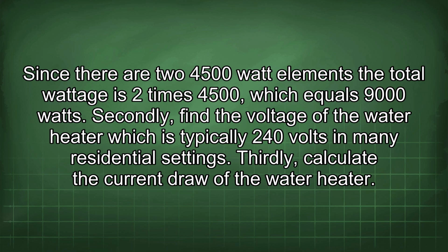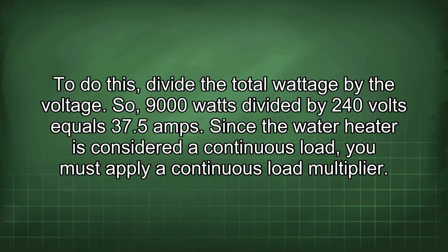Secondly, find the voltage of the water heater, which is typically 240 volts in many residential settings. Thirdly, calculate the current draw of the water heater. To do this, divide the total wattage by the voltage. So, 9,000 watts divided by 240 volts equals 37.5 amps.